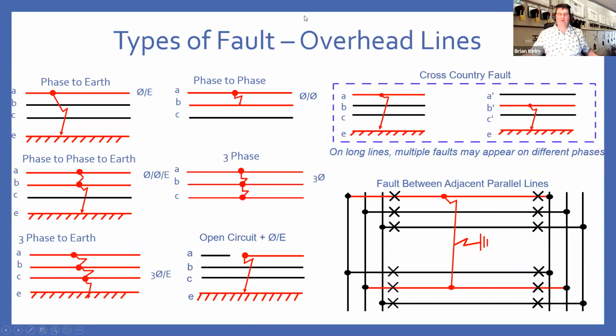So here's a nice busy slide on types of fault. We start on the left. These are all the combinations of fault to earth. So you can have a single phase to earth, a phase to phase to earth, and a three phase to earth. And you could find that a fault starts as a single phase to earth and evolves through to the three phase to earth if your protection hasn't detected. You may also get faults that are just between two phases and doesn't go to earth. And that again may evolve into a three phase fault, but with no earth current flowing.